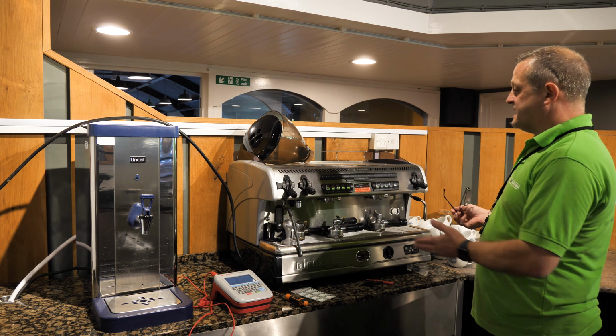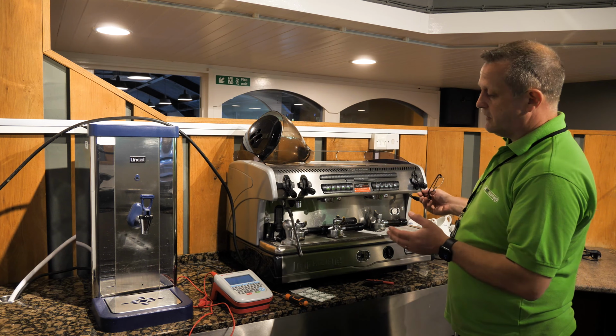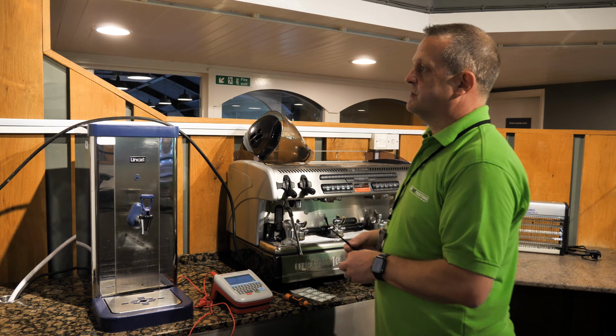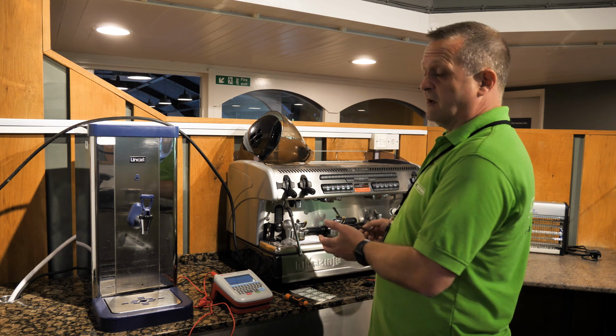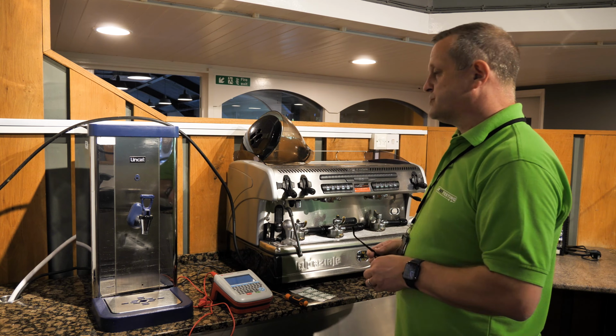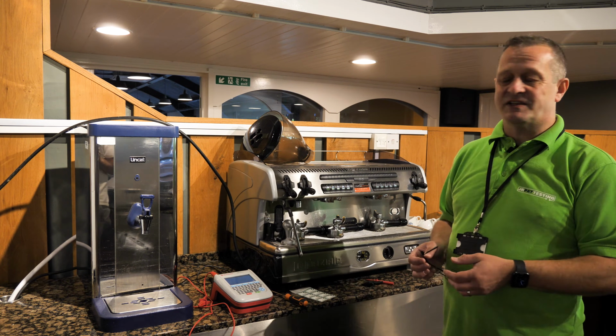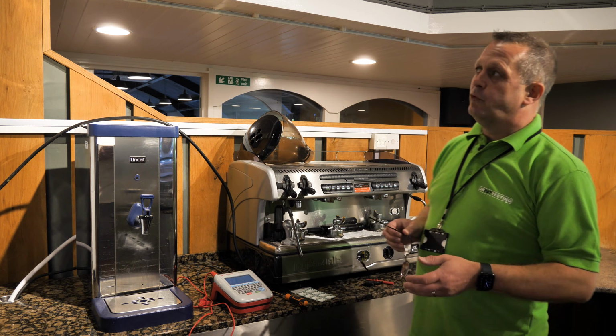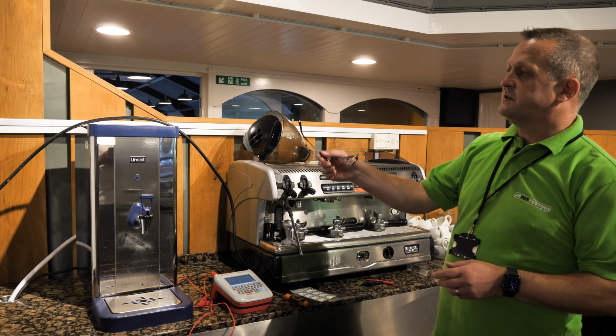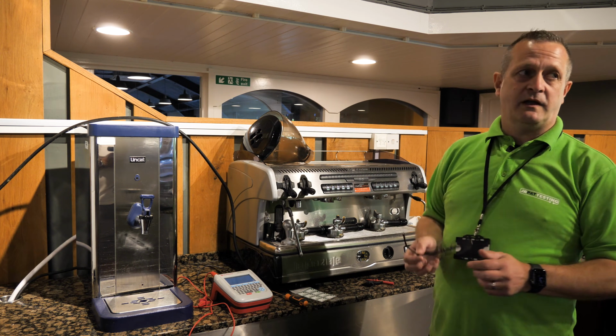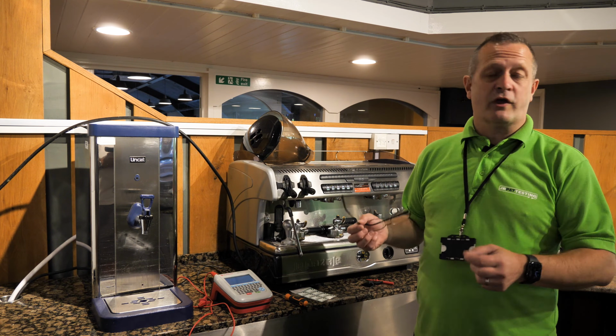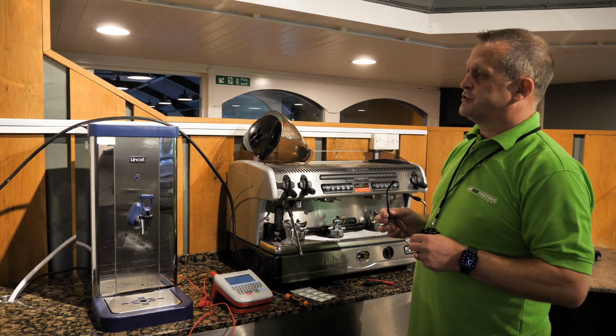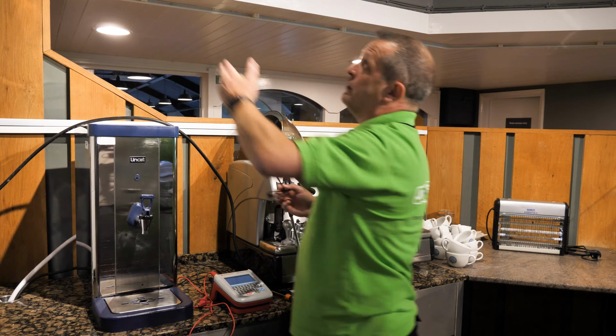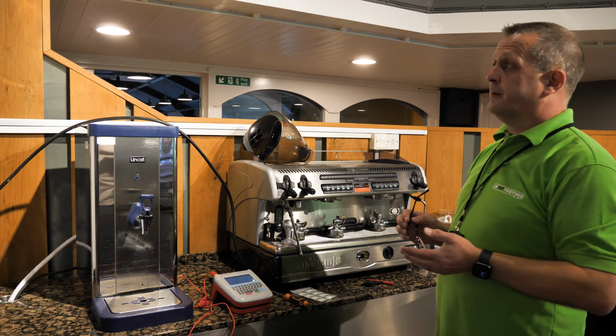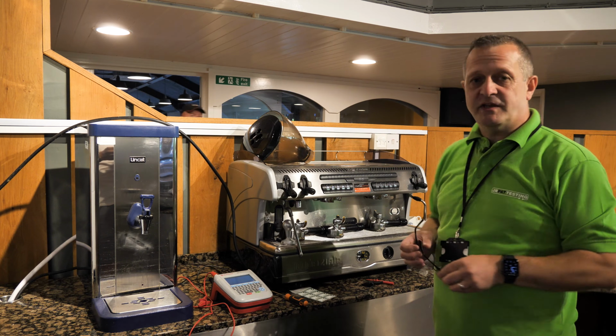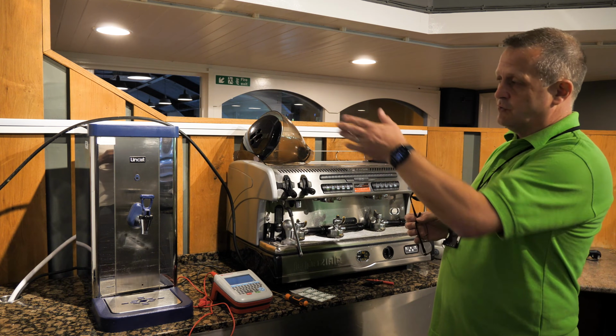So now we're going to be looking at testing this coffee machine. It's a rather large appliance, and on this particular occasion it doesn't have a plug, which means testing it is somewhat different. It's still treated as a class 1 test, but we're going to treat it as a fixed appliance. Normal procedure for a fixed appliance test would be to isolate the appliance at the main consumer unit, and we would go through a lockout procedure with the consumer unit. However, looking at the cable in here, I can't ascertain where the consumer unit is, so we're going to do a basic earth continuity test using the spur switch.